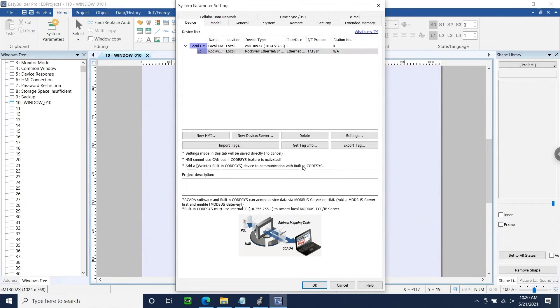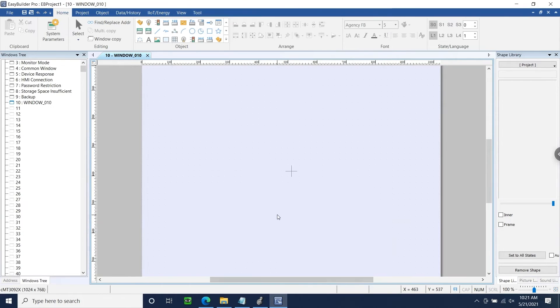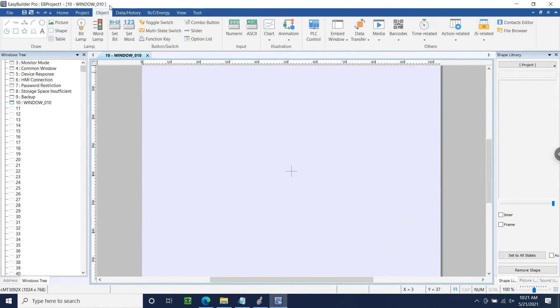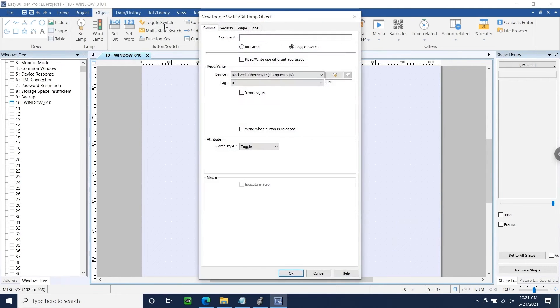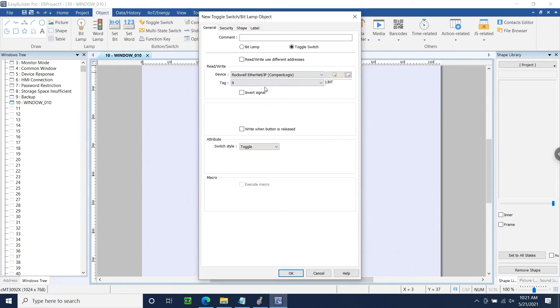Let's close our system parameters and test communication by assigning our Run tag to a toggle switch. To do this, I'm going to select the Object tab, and on the top left, I'll click Toggle Switch. Within the Device drop-down list, I'll ensure that the driver for our Compact Logix is selected.